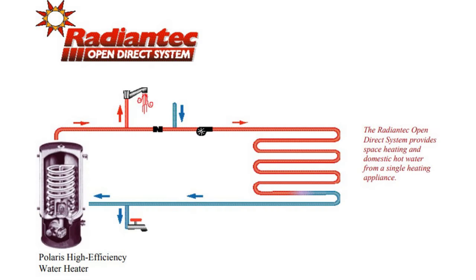And then as far as the heater goes, I'm still not 100% certain on this. There's a lot of good ways to do this. You could use a tankless water heater and do a closed circuit for just the floors. And then something else that Radiantec recommends is they call it the open direct system, where you use one hot water heater that's rated for both your standard water heater needs for your house and for floor space heating. It actually runs in one big open loop. All the floor water is actually potable, and it serves a little bit of double duty because in the summer when you're running hot water, it pulls some of the heat out of the floor and does do a little bit of cooling in your floor.